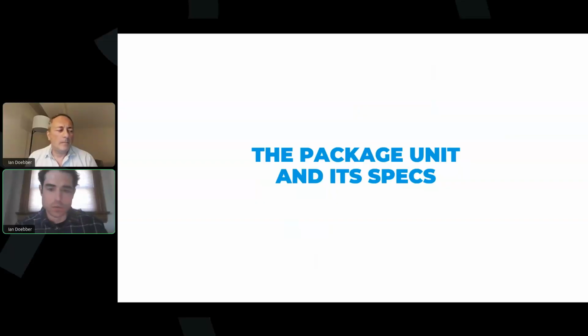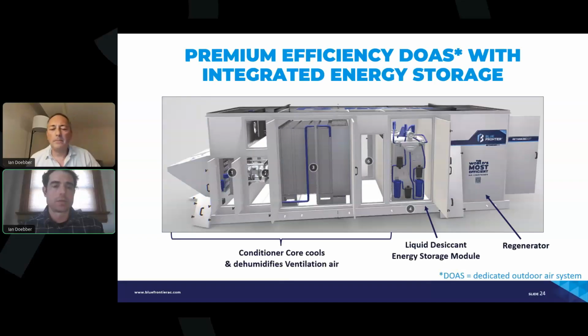Now we're going to jump into the packaged unit itself and its specs. This is the unit, what it looks like. On the left you can see the conditioner core, which is essentially like a fan coil unit. The air is blown by the fan, number 2, through the heat exchanger, number 3, and then pushed into the supply plenum, number 6, and delivered to the building. That part of the system is doing the cooling and the dehumidification.